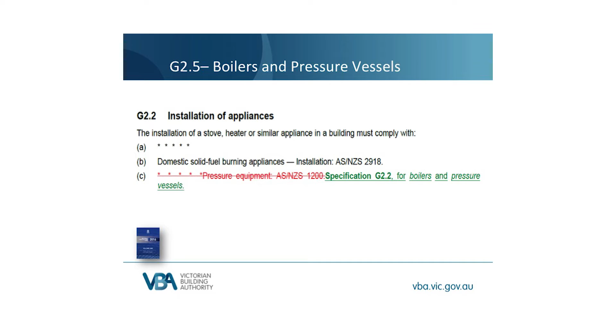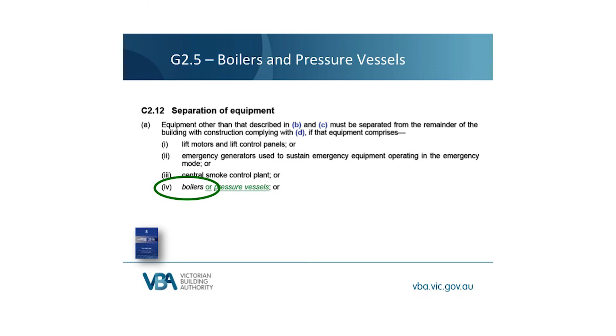Incidentally, now the boiler is a defined term, the ABCB have taken the opportunity to clarify C2.12, separation of equipment, by italicising boilers in C2.12(a)(iv). This clarifies that a hot water heater, say in a mechanical ventilation system, which doesn't heat water beyond 100 degrees C, does not require fire separation.